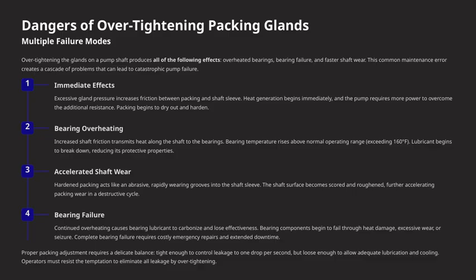This increased friction and heat also cause the shaft to wear out faster. The hardened packing acts like an abrasive, gouging grooves into the shaft sleeve. Over time, this results in a scored, rough shaft surface. This damage then speeds up the packing's wear, creating a destructive cycle that's hard to stop.